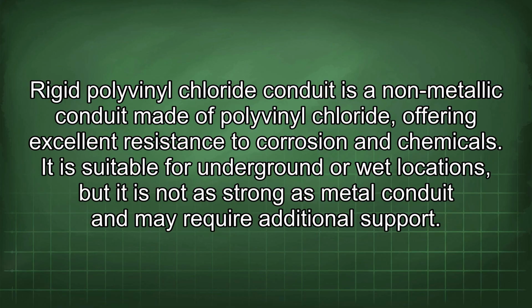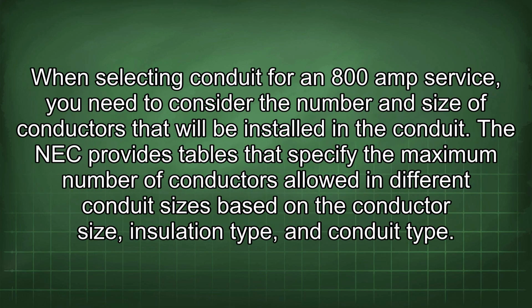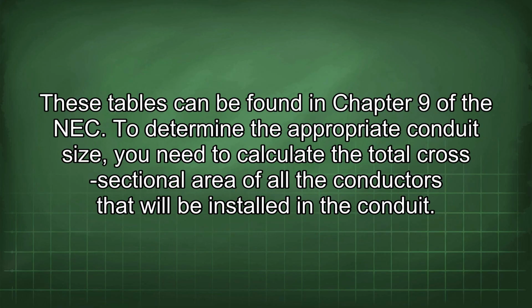additional support. When selecting conduit for an 800 amp service, you need to consider the number and size of conductors that will be installed in the conduit. The NEC provides tables that specify the maximum number of conductors allowed in different conduit sizes based on the conductor size, insulation type, and conduit type. These tables can be found in Chapter 9 of the NEC. To determine the appropriate conduit size, you need to calculate the total cross-sectional area of all the conductors that will be installed in a conduit.